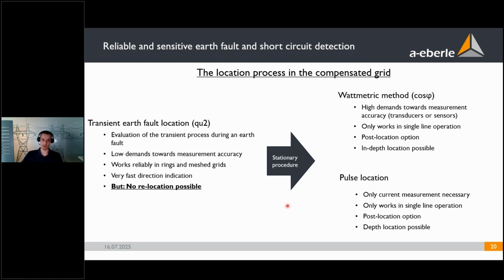That's why you will need a stationary procedure. For example, the watt metric method or the pulse location. The watt metric method, or cosine phi method, does have high demands towards measurement accuracy, no matter if you use transducers or sensors. So for both voltage and current measurement, high demands. It only works in single line operation, and it has this post location option for in-depth location.